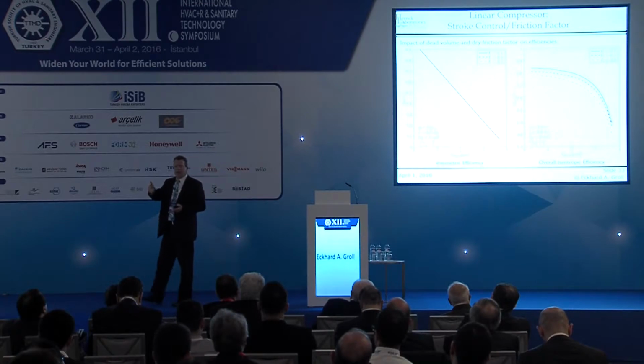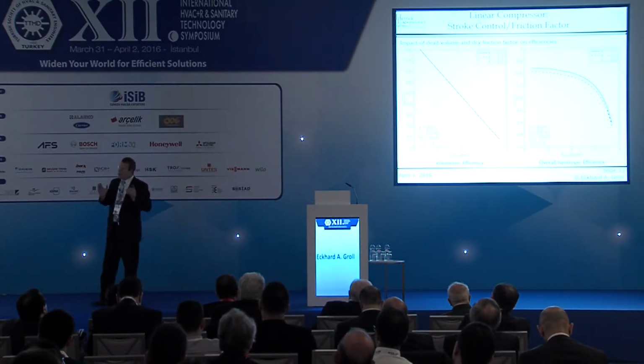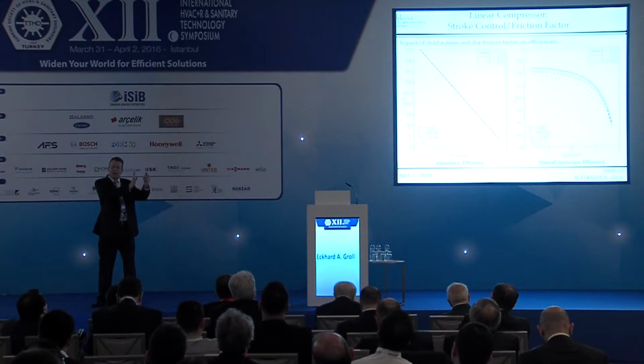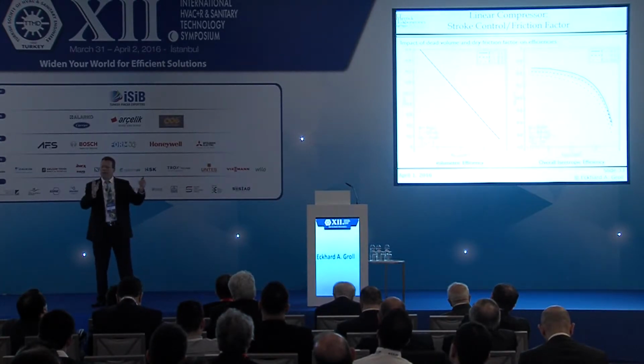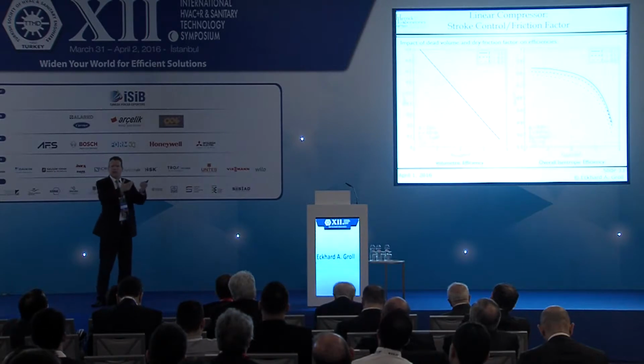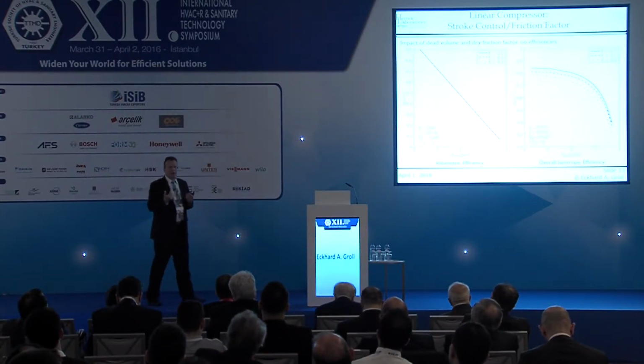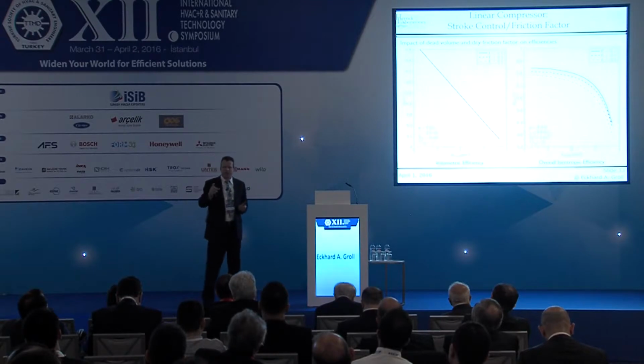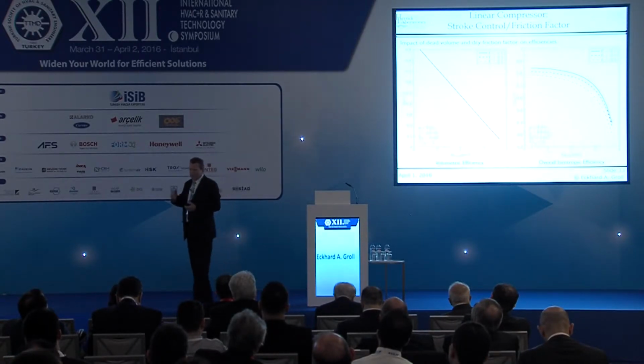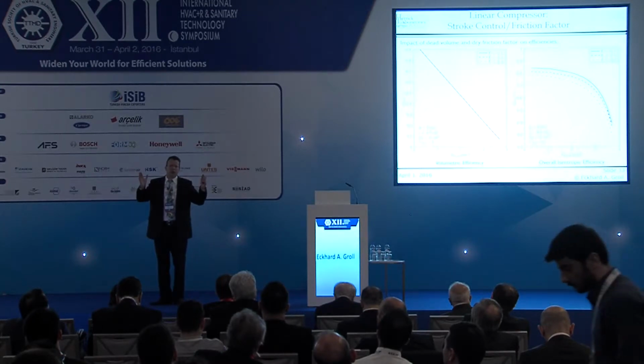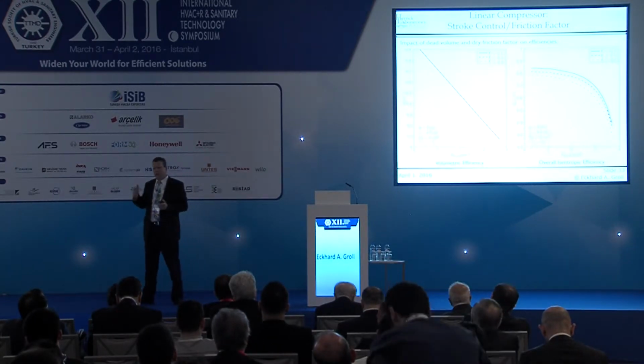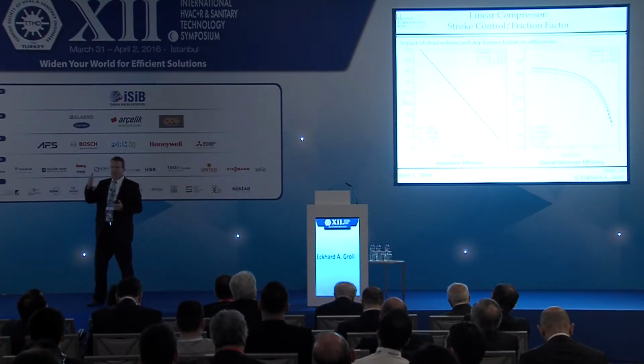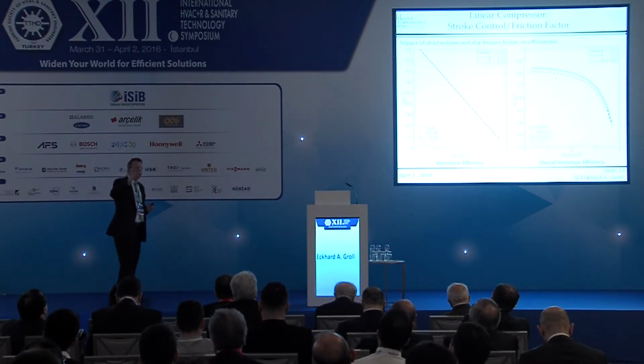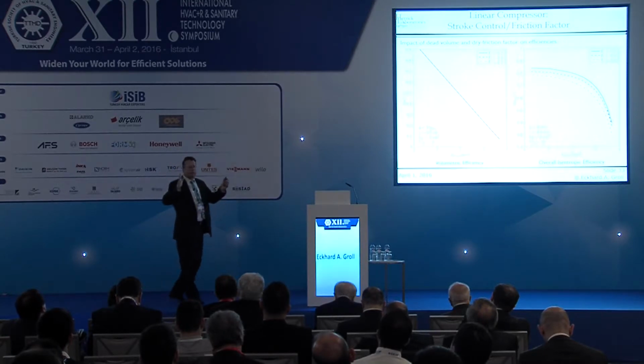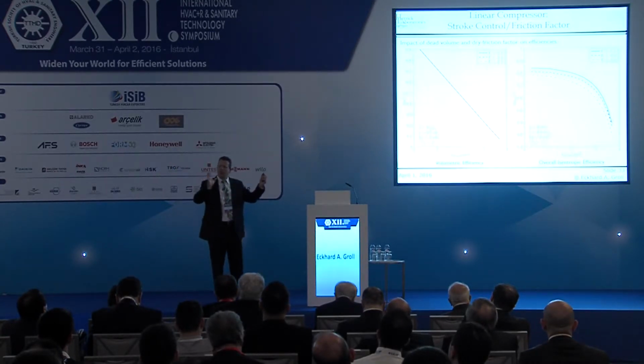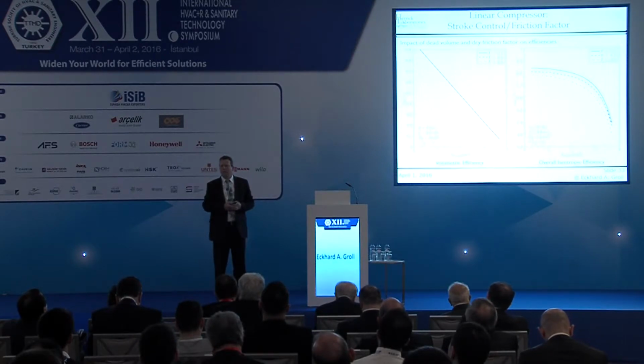This is not the case in a linear compressor. If I compress the gas and don't push it out, it comes back in the form of spring force. I can recover some of it inside the spring, not 100%, but some, as shown on the right-hand side. I can have a larger clearance volume, not moving the piston all the way up, but still maintain relatively high overall isentropic efficiencies across a range of clearance volumes, meaning I have a means of capacity control.